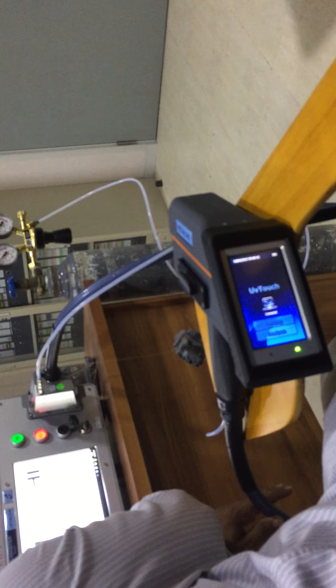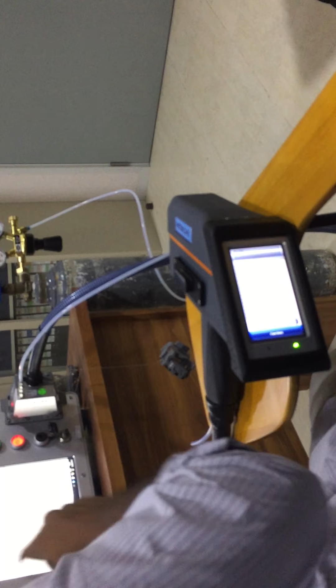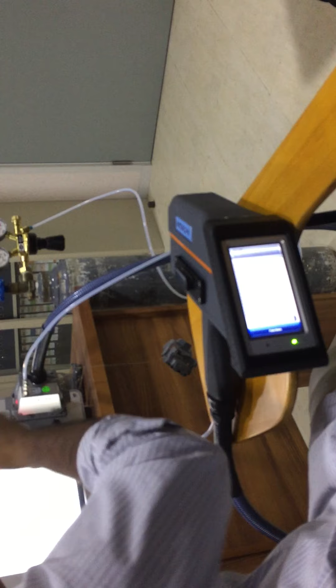So now you can go to analyze. Now you clean the sample. When you're sparking, you need to get the sample spark like this, black with white. If you're always getting pure white, maybe the argon gas quality is poor, so you need to check that. After that you need to clean the surface with grade 60 wheel. Grade 80 is fine, but grade 60 you want to use for the OES. Also, whenever recalibrating on site, mostly you need to change the papers. Otherwise, you will get more variation in the values.